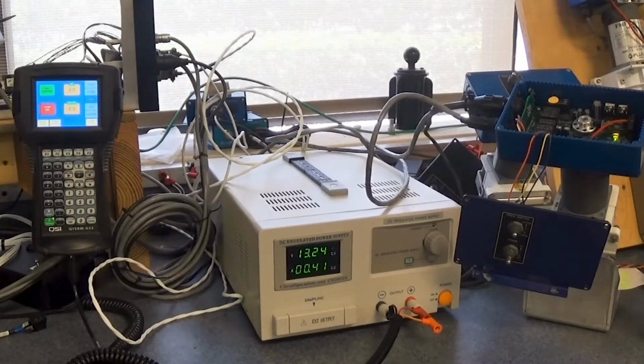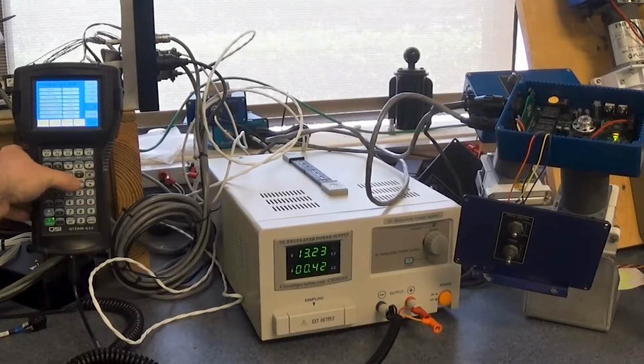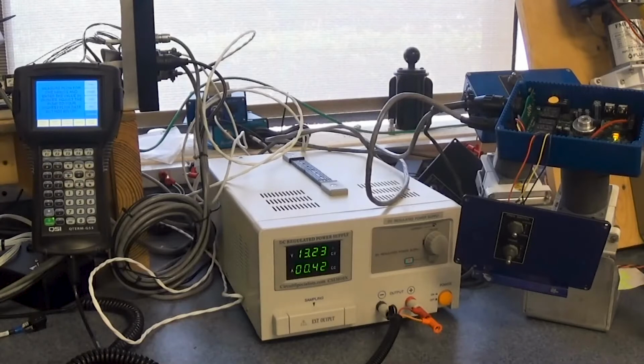Another thing that you may note is if you were to go down into calibration, obviously making sure that your plumbing is going into some sort of a catch can, because the pump is moving. But what you'll also notice here in calibration is we have a pulse per second count, a pump PPS of 0.0.